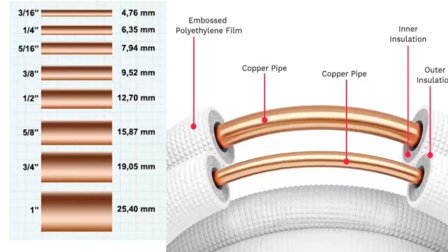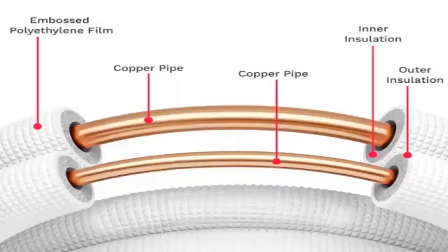9. Respect the original pipe diameters of the equipment and cut unnecessary lengths to reduce pressure drops within the pipes, thereby increasing system efficiency. 10. Properly and independently insulate the pipes of the equipment to prevent condensation points from the outside air and maintain good efficiency.